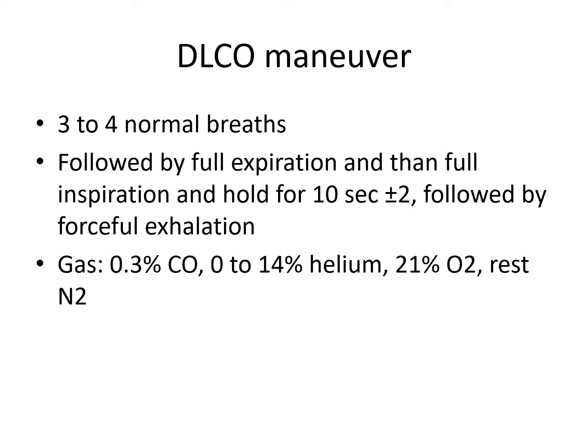Initially, the subject will take normal breaths, about 3 to 4. This is followed by full expiration and then full inspiration and breath holding for about 10 seconds, plus or minus 2 seconds, followed by forceful exhalation. During this maneuver, the subject is going to inhale a gas of 0.3% carbon monoxide, 0 to 14% helium as tracer gas, 21% oxygen and the rest nitrogen.